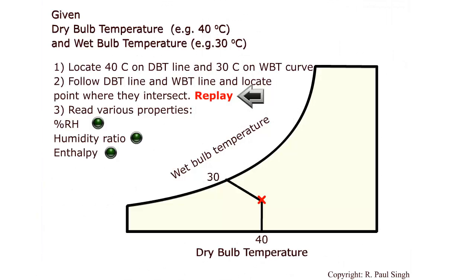Let's say that we know the dry bulb temperature and wet bulb temperature and we want to locate a point on the psychrometric chart to determine all the remaining properties. In this example, the dry bulb temperature is 40 degrees C and wet bulb temperature is 30 degrees C. We locate the vertical dry bulb temperature line and the inclined wet bulb temperature line and see where those two lines meet.